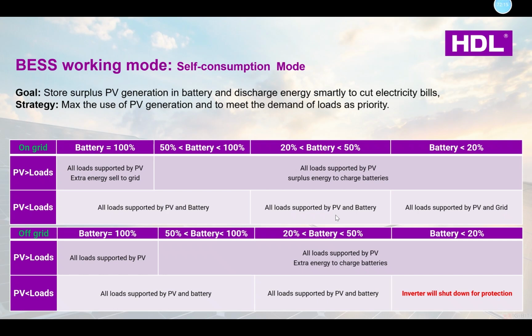First of all, I would like to introduce the working modes of the BESS system. Generally, it has two right now. The first one is the self-consumption mode. What is self-consumption? The inverter will provide the solar power to feed the home loads as a priority. If you still have surplus power, it will start to charge the battery. After that, if you still have surplus power, it will export the energy to the grid. So this is the working logic of self-consumption mode.